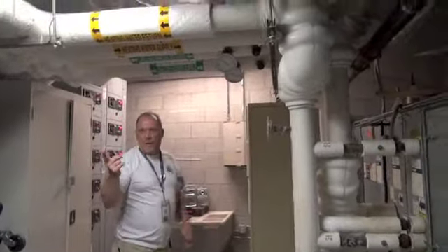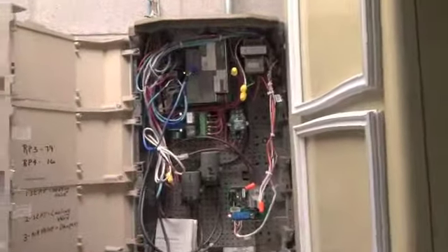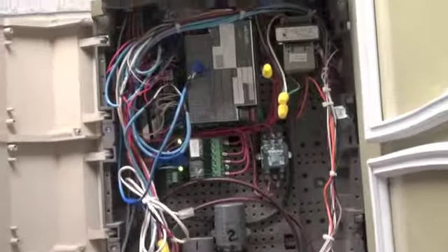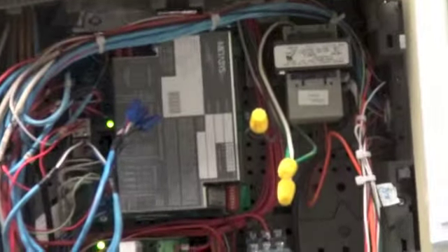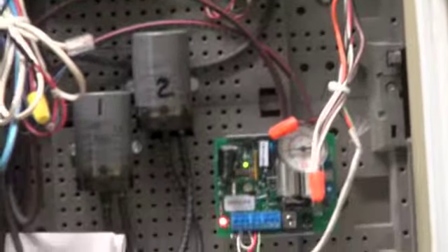As I was talking about in there with the control system, this is the controller here that controls this unit, which talks to the front end where we were just at. I can manipulate any point. I can tell the dampers to open, dampers to close, raise and lower the set point in the space. That simple little controller controls this unit, and it's the brain of the control system for this unit.